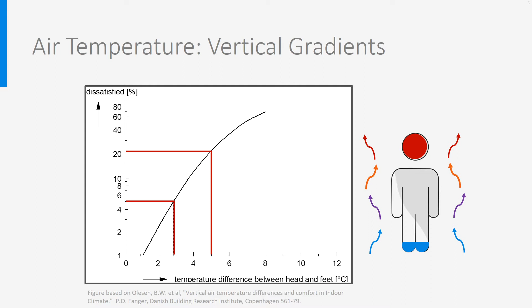We saw in another lecture that people are sensitive to too high air speed. Sensitive spots are the neck and the ankles, and we named this discomfort draft. A general rule is that the airspeed should be lower than 0.15 meters per second in winter, and a higher velocity is allowed in summer. But draft depends also on the turbulence of the air. Turbulence is a measure for changing speed and direction of air flows.